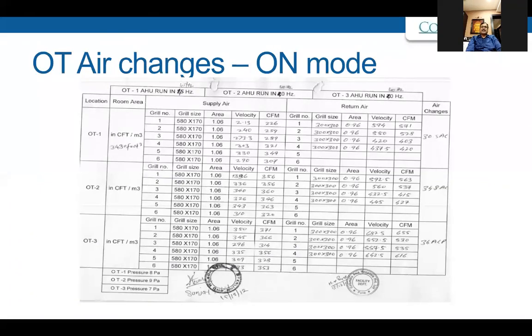So this is just an example to show you the actual test results given by a vendor for a particular operation theater complex. That is, 3 OTs are there. They have given various values. This is just for your consumption, that it checks your velocity, it checks your particle count at every point, and there are 4 or 5 points which are taken for doing air particulate test, based on which the combined results are taken out. Next, please.